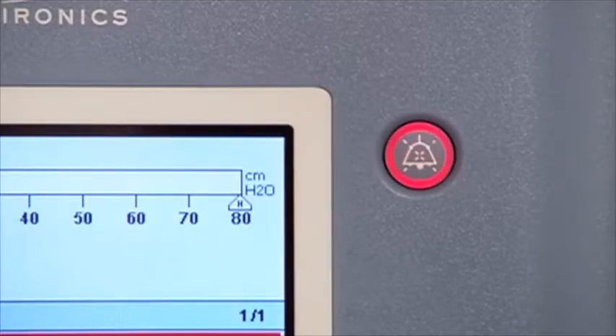High priority alarms sound like this. That's 3 beeps followed by 2 beeps. At the same time that the alarm sounds, the audio pause button on the front of the ventilator flashes red. When you hear or see a high priority alarm, respond immediately, as a high priority alarm alerts you to critical issues with the patient's breathing or with the ventilator's operation. Always look at the patient before attending to the equipment to ensure that he or she is being properly ventilated. If not, use a manual resuscitator to help the patient breathe. When you are sure that the patient is stable, turn your attention to the ventilator.